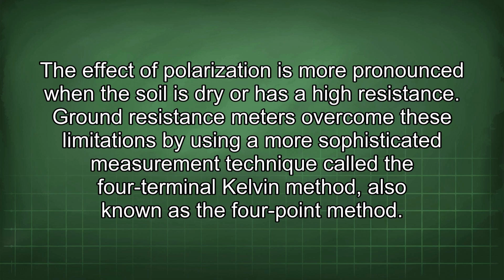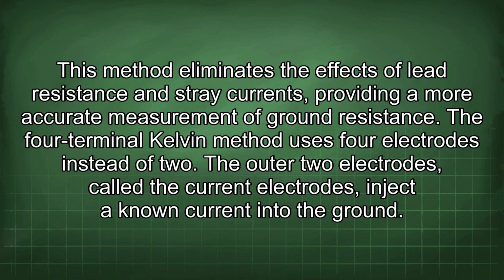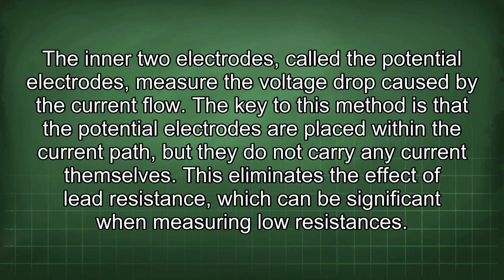Ground resistance meters overcome these limitations by using a more sophisticated measurement technique called the 4-terminal Kelvin method, also known as the 4-point method. This method eliminates the effects of lead resistance and stray currents, providing a more accurate measurement of ground resistance. The 4-terminal Kelvin method uses 4 electrodes instead of 2. The outer 2 electrodes, called the current electrodes, inject a known current into the ground. The inner 2 electrodes, called the potential electrodes, measure the voltage drop caused by the current flow.